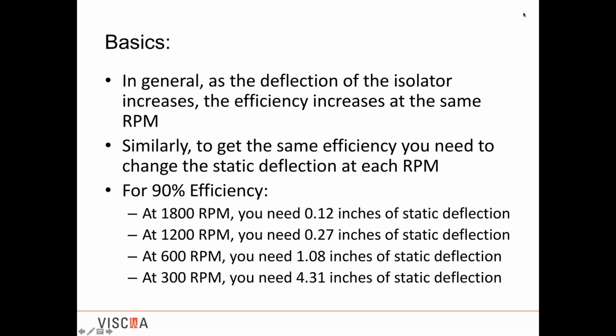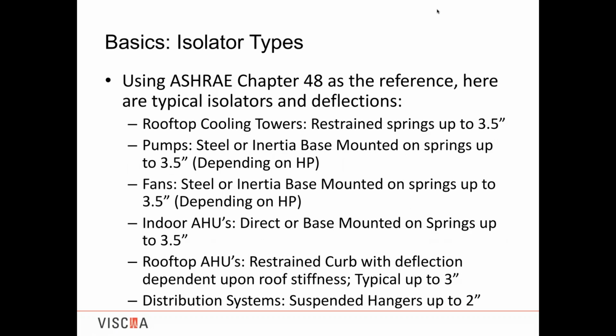In ASHRAE Chapter 48, and generally in our industry that VISCMA deals with, we discuss inches of deflection and RPM. We do not get into hertz or cycles per second as would be done analytically. Using RPM and inches of deflection is equivalent analytically to going into hertz, but it's not necessary, since this is the information most people will get from a manufacturer: the RPM of the motor, and from the manufacturer of the vibration isolators, such as Kinetics and VMC, the inches of deflection of our springs. So ASHRAE Chapter 48 relates those two rather than going into frequencies in hertz and cycles per second.